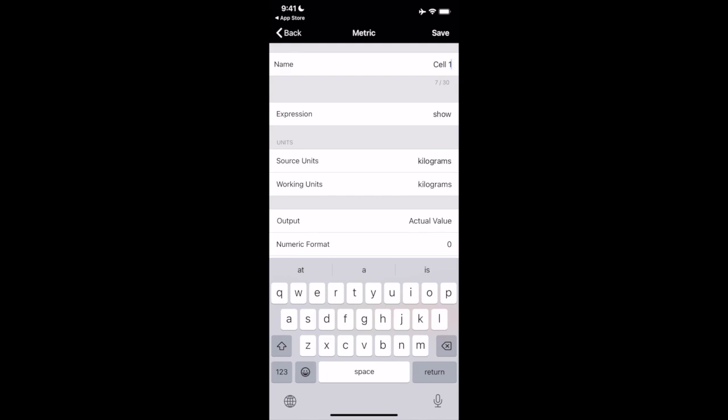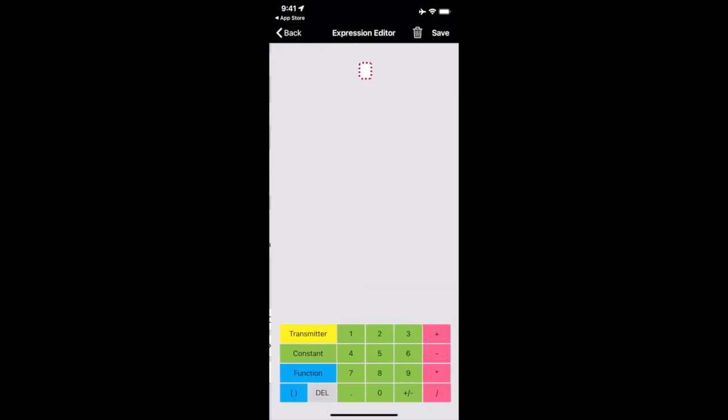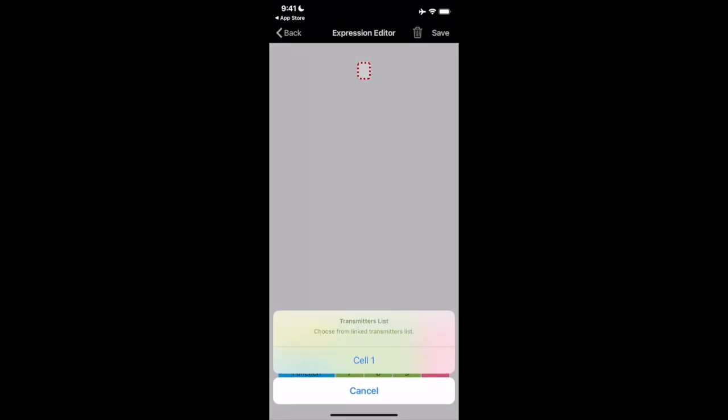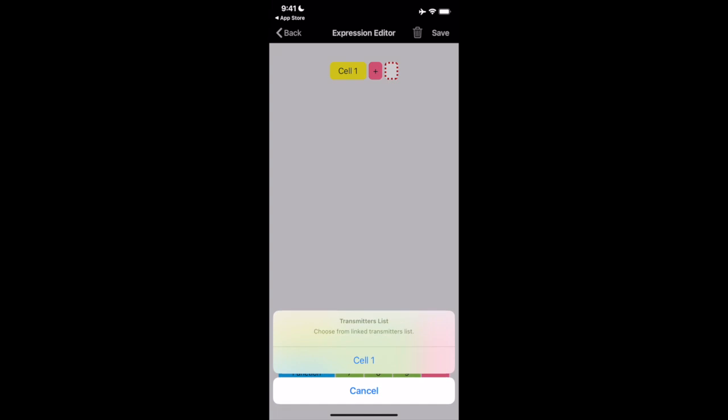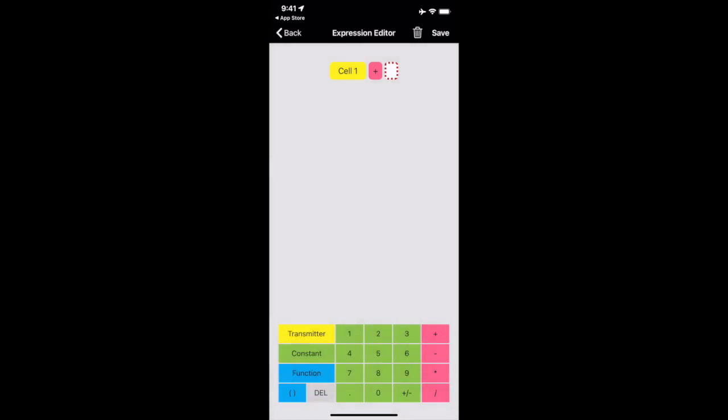So we're going to call this cell one, expression is what load cell it's looking for. So in expression, we're going to click on that. We have our kind of editor in here. So, it's pretty basic. Think of kind of using a calculator, except for you're adding load cell, you know, choose a function like load cell plus load cell for your total, anything like that. So I'm going to do transmitter. I'm going to see all my transmitters in here. For this one, we just have one cell. So cell one, and that's perfect. If I were doing a total weight off something, I would do transmitter plus transmitter, let's say cell two, et cetera. And I would just keep moving down the line, but I'll delete that right now because we just have the one load cell. So it's pretty straightforward for what you want to do, whether you want to do something simple or complicated. So we have cell one. We'll save.